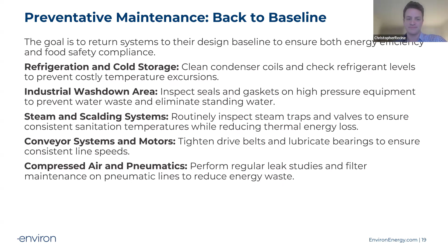And then lastly, compressed air, which is usually specific to pneumatic equipment. Making sure that you are doing regular leak studies at least every other year, ideally every year, and making sure that the filters and the maintenance are done, as well as on the dryers for your compressed air system. The fun test for compressed air is to go in when there's no production, when the lines aren't running, and see how many compressors are running. See how much the system needs to be on just to maintain the pressure of the lines without any pneumatic air actually being used. I think that can usually be very telling. Sometimes we see 2 or 3 compressors firing regularly, even though there isn't a single piece of equipment being used in the plant.